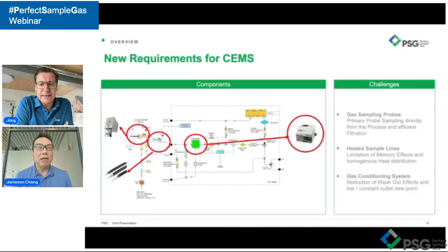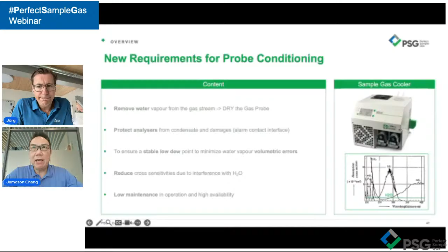Why does PSG have such a big family of gas coolers? The most important thing in the gas cooler, to answer your question, York, is about hot wet and cold dry. It is really about how we address the solubility of the gases. If the gas is dissolved or washed out during the gas cooling, and we are going to measure this gas, then we choose to have a hot wet system without a gas cooler.